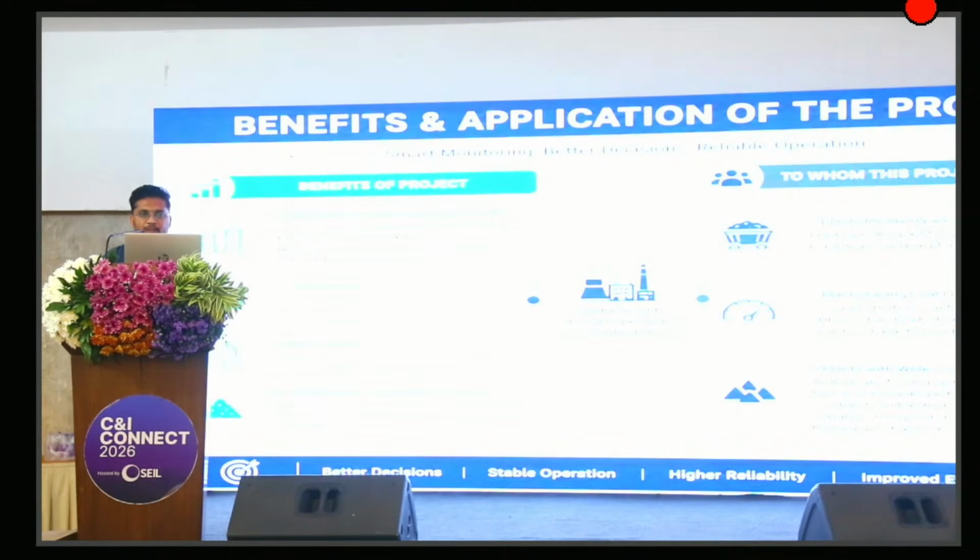So this project was used to better the mills standby strategy during NLD. During NLD, high quality mills were kept standby, because during full load condition, whenever the quality of coal was low, we'd have coal flow restrictions from ash handling constraints. Due to this, whenever there is NLD, we keep higher quality mills as standby and take lower quality mills into service. So this project gives us accurate load prediction, minimizes RDs, and can also be used to identify high slag index in the coal sources.